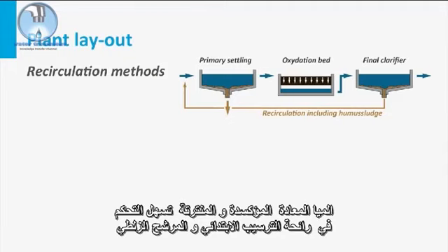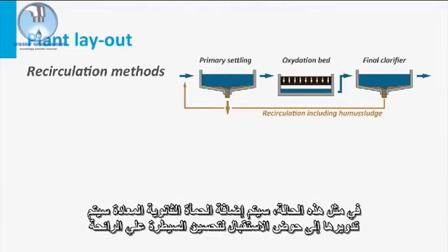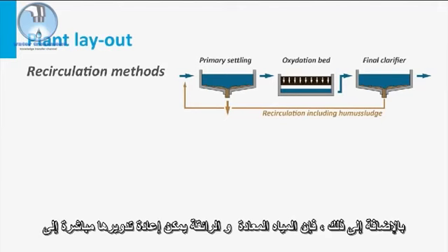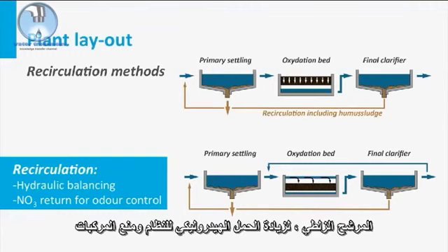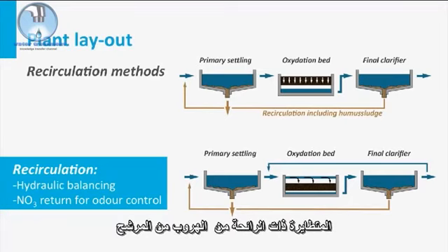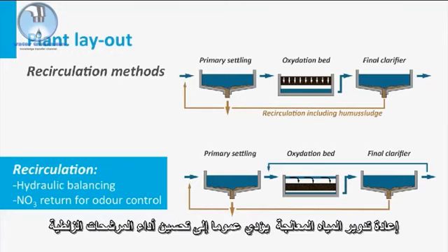The oxidized nitrified effluent facilitates odor control in the primary clarifier and the trickling filter. When connected to a gravity sewer, the primary clarifier is preceded by an influent reception basin. In such case, the recycled secondary sludge will be added to the reception basin for enhanced odor control. Additionally, the nitrified and clarified effluent might be directly recycled to the trickling filter to increase the hydraulic loading and to prevent volatile odorous compounds escaping the filter system. Reduced volatile compounds such as sulfides are then oxidized by nitrate.